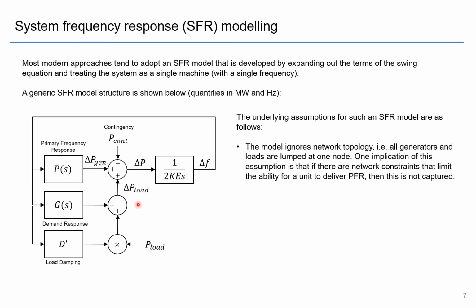The model really ignores all network topology, so we're not even looking at transmission lines, substations, or anything like that. We're just lumping it all into a single node. So all generation, all loads, all just hanging off the same node. But one implication of this assumption is that if there are genuine network constraints that limit the ability, for example, for a unit to deliver primary frequency response because it is across a transmission line which is constrained, or it could be even tripped off, then this is really never captured in an SFR model.